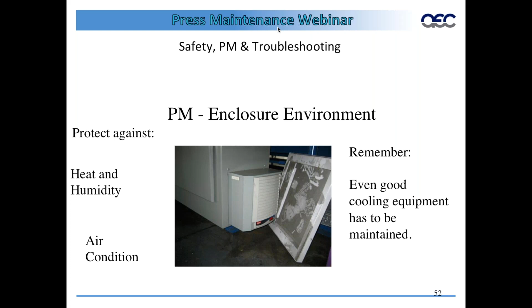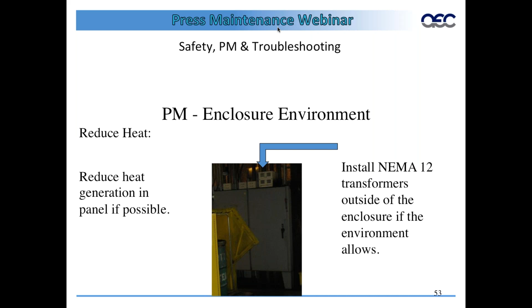One way to prevent heat buildup inside panels is to get the items that generate a lot of heat out of the panel, so you don't have to work as hard to remove heat from it. Here's a picture of some transformers on top, a different NEMA rating that can sit outside the panel so they dissipate heat without putting it all into the panel.